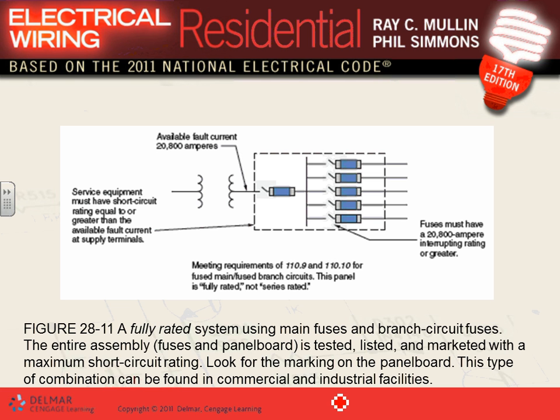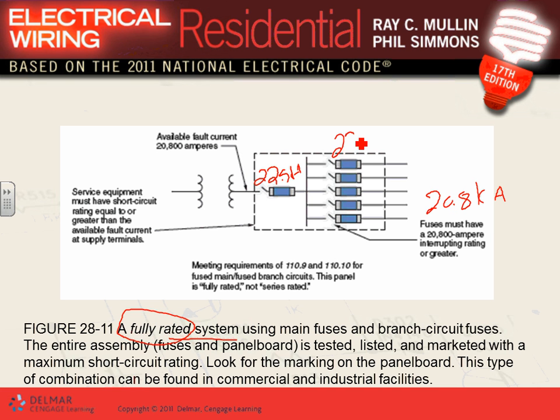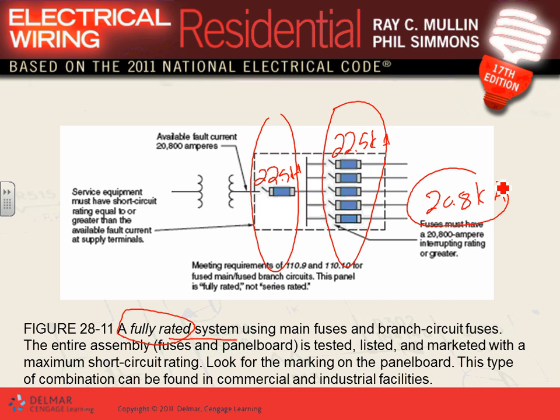Here's a fully rated panel. The available short circuit is 20,800 amps. Each one of these circuit breakers or fuses is rated for 22,500 amps. If the branch circuits and the main are both rated to handle the short circuit on the branch circuit side, this is a fully rated system. The problem with fully rated? Big dollars.